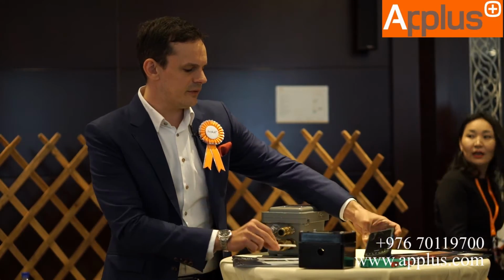We also have RFID tags, which using the PDA we can use to record our inspections. Using the software developed, we can carry out a risk-based inspection program to actually reduce the amount of inspections that you need to carry out on a yearly basis. Using the RFID software, we can cut down on the time required, and you can see an online real-time status of your plant and operations, along with pictures, defects, what you need to do, materials required to order, and how to repair those defects.